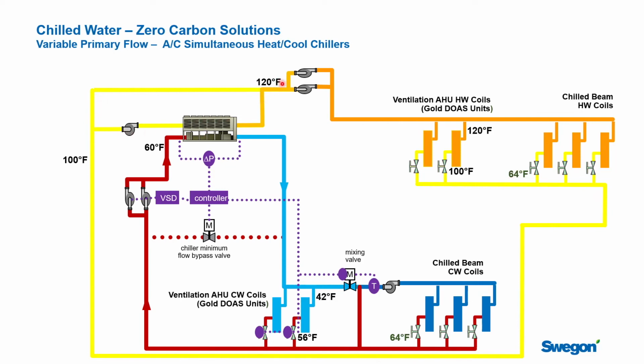So this is a heat recovery system, air-cooled style, that allows you to move heat from around in the building. If you have a surplus of heat, you reject it to atmosphere. If you have an absence of heat overall in the building, this will run in heat pump mode, extract the heat back out from the air, and use that to heat the beams.